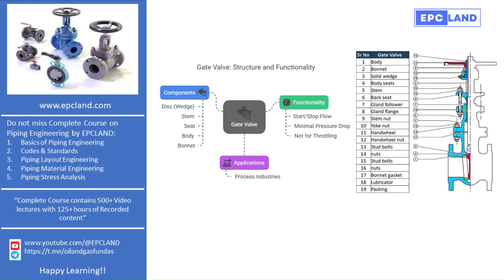However, when you want to shut off the flow, the gate lowers down and makes full contact with the seat. To create a proper seal, the gate must make 360-degree surface contact with the seat inside the valve. This ensures a tight shut-off and prevents leakage.